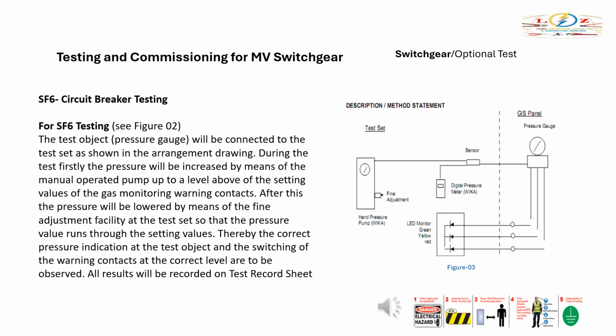SF6 testing, Figure 2. The test object, pressure gauge, will be connected to the test set as shown in the arrangement drawing. During the test, firstly, the pressure will be increased by means of the manually operated pump up to a level above the setting values of the gas monitoring warning contacts. After this, the pressure will be lowered by means of the fine adjustment facility at the test set so that the pressure value runs through the setting values. Thereby, the correct pressure indication at the test object and the switching of the warning contacts at the correct level are to be observed. All results will be recorded on the test record sheet.